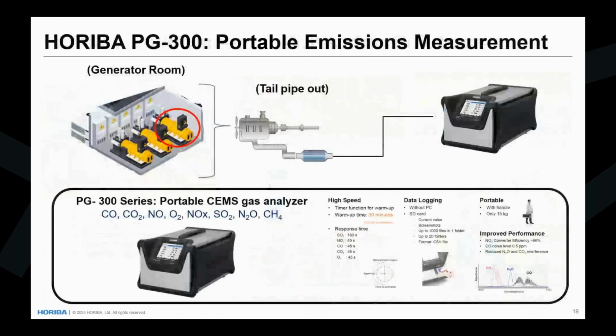What I'd like to talk about next is the HORIBA PG300 series portable analyzer. And the reason this analyzer was designed is HORIBA understood that not every application requires a permanently installed analyzer. But also that a portable analyzer that can measure combustion measurements, have a self-contained onboard sample system, could be used for commissioning, troubleshooting, maintenance, as well as verification activities. This PG300 was actually configured to measure multiple gases simultaneously. We can put 5 different measurements inside a single unit. Those measurements, there's some pre-configured combinations of measurements.